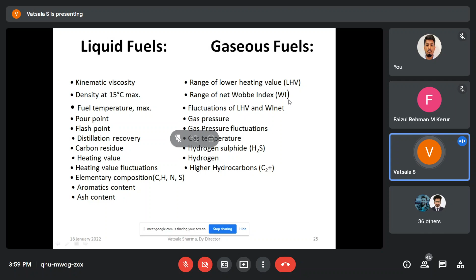Impurities which will be available in the liquid fuels and the gaseous fuel. Gaseous fuels: dust content, maybe particle size of the dust, relative humidity, how much it will be. Because when I am talking about the gas power plant, we have to see the pressure, temperature, and relative humidity. These are considered as the ISO parameters for the gaseous fuels. And then trace elements also sometimes we consider, but rarely. Trace elements are also considered in the liquid fuels. Water and sediments, whether impurities are available or not, are important parameters when you are doing the analysis of any fuel.